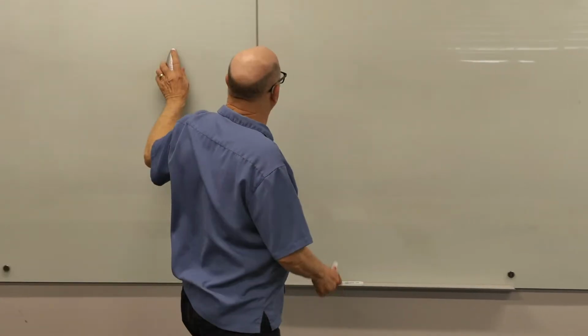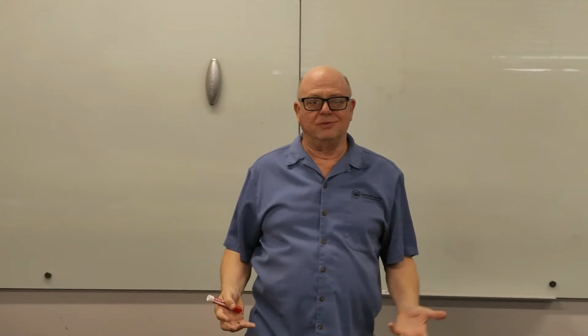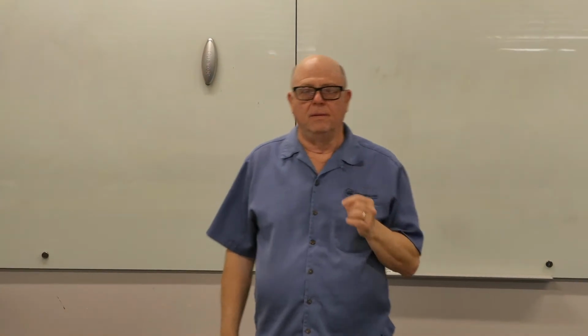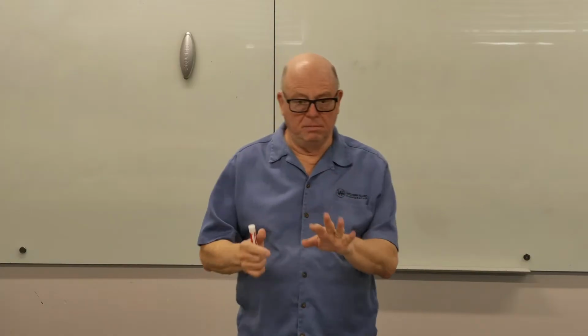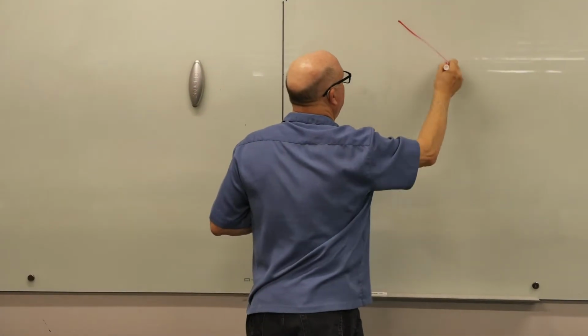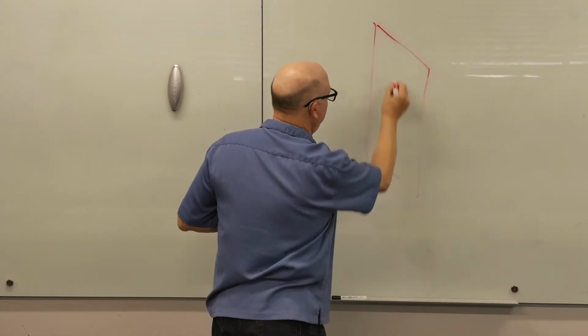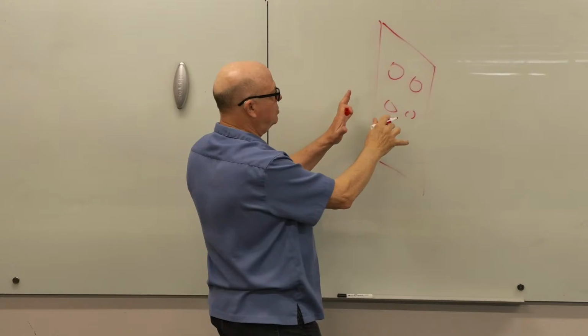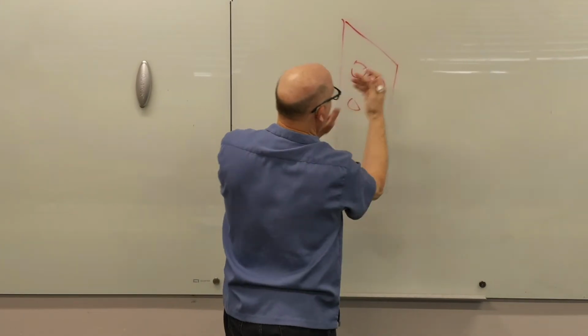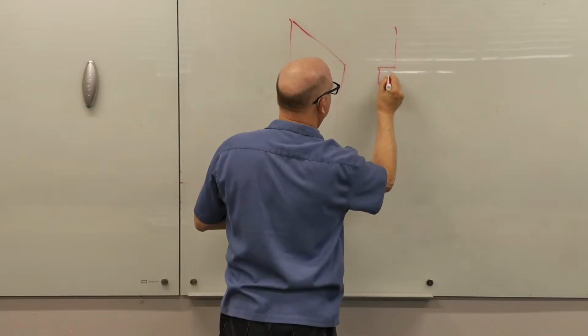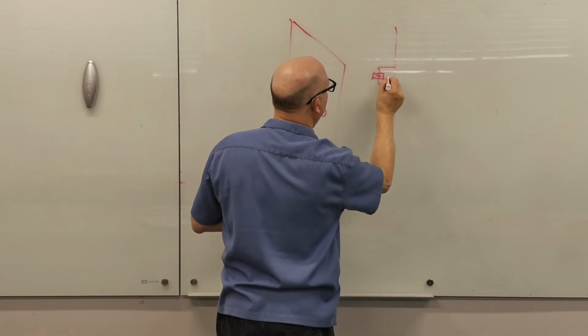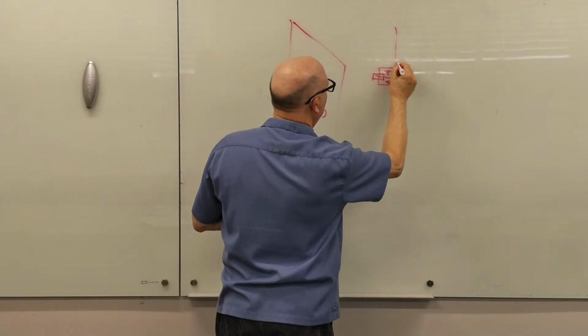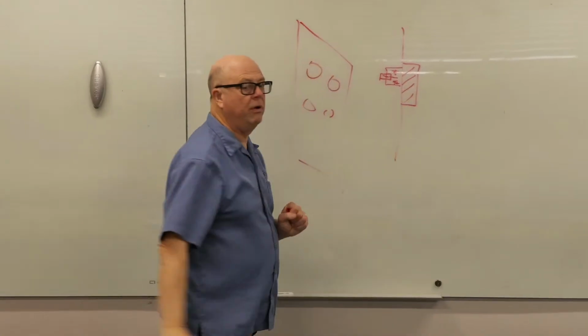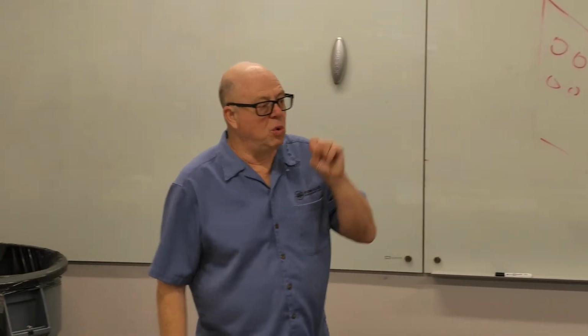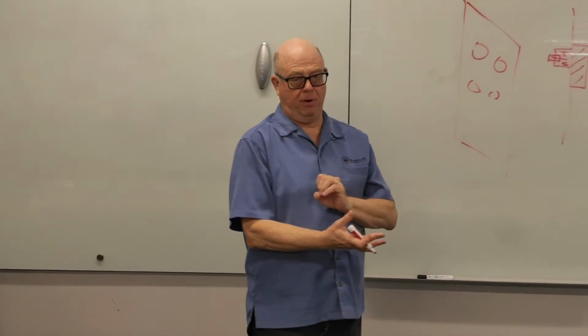Okay, so the fan wall is just a wall of fans. And they are single inlet, they're pressurizing the plenum, and the duct goes away. They are less efficient. They can be pretty good to control. But remember, we were talking about how they will spin backwards. And so if you've got a fan wall with a bunch of fans, on the discharge side, if we looked at that on the end, here's our fan sitting here, right? The motor and a fan wheel. We have to put a motorized damper on the discharge of every one of those.